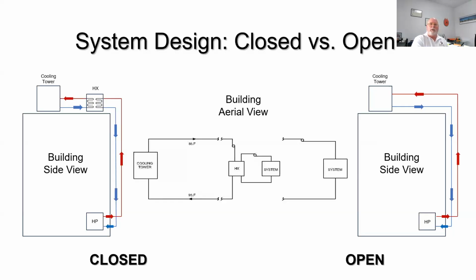On the other hand, buildings built in the 70s, 80s, even into the 90s were built with an open system. On the right side here, water comes from the cooling tower down into each individual air conditioning unit and back up into the cooling tower. The problem is that instead of keeping dirt and debris up on the roof or in the heat exchanger, it's now spread throughout your whole system.